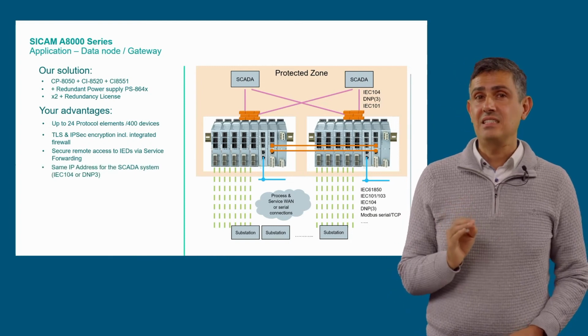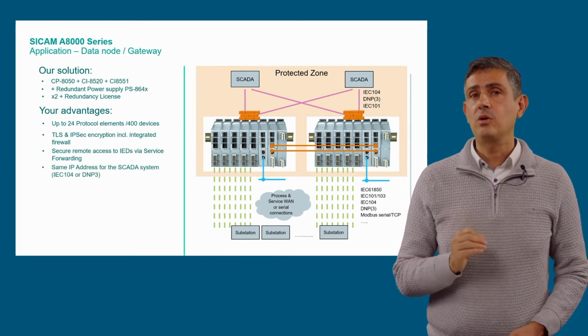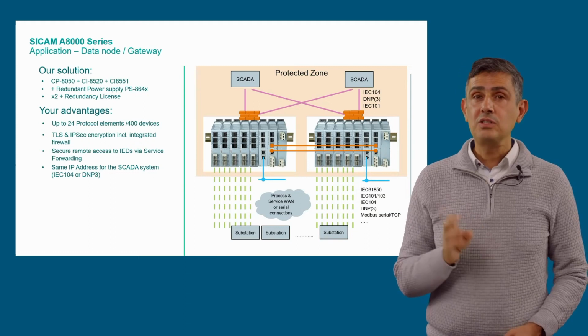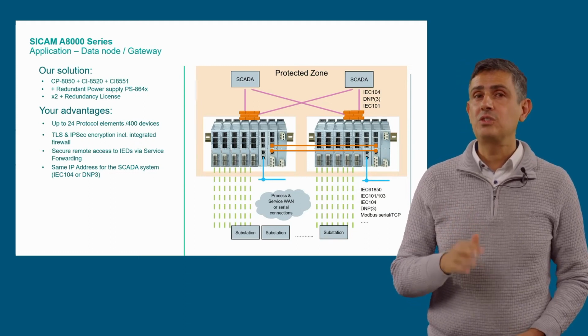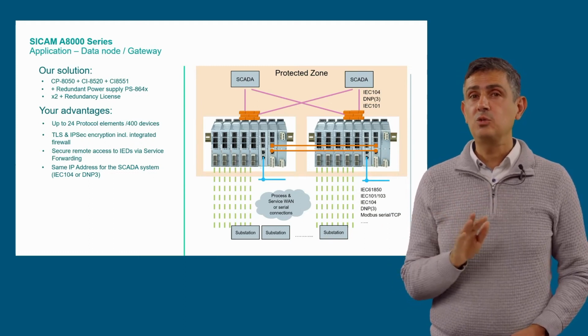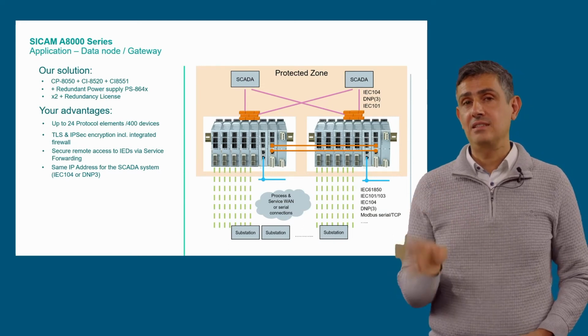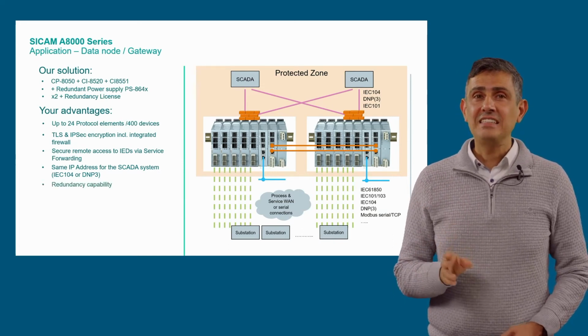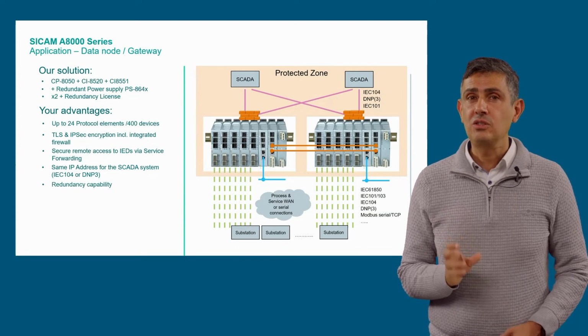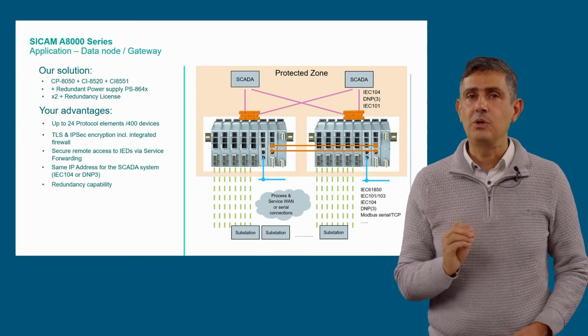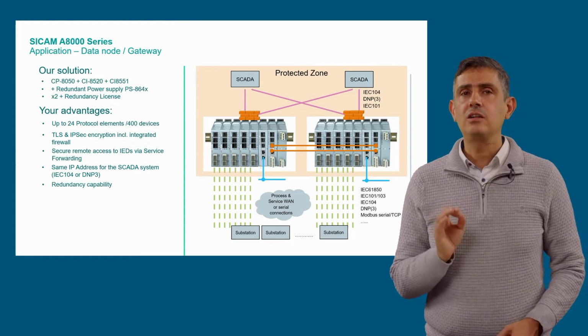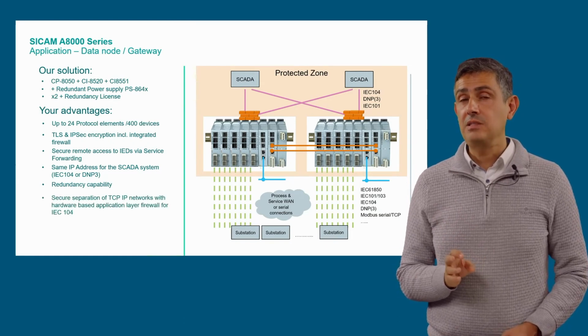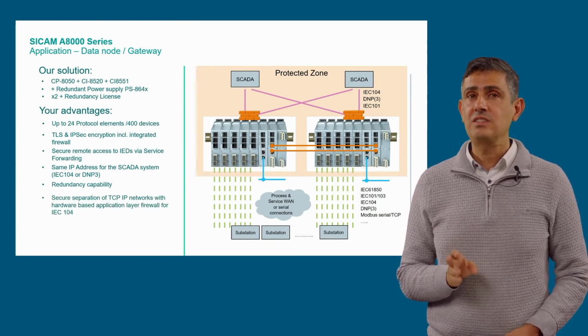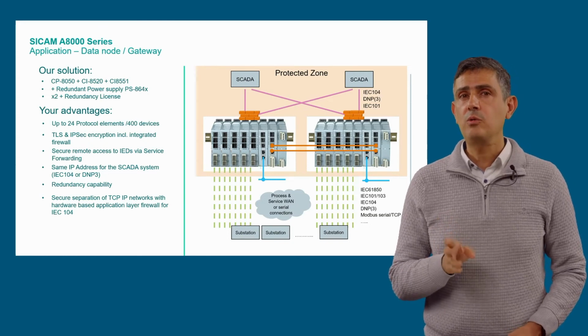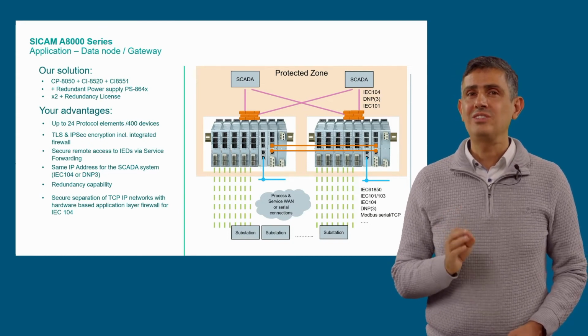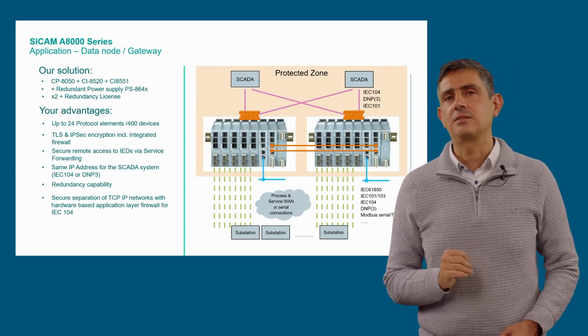If the master system uses the communication protocol IEC104 or DNP3, it is possible to manage the same IP address on both CP8050, so both data nodes will be seen as a single one by the master system. The fact that the redundancy is firmware-based ensures that its implementation is very simple and that it works only under proven algorithms. The CP8050 can also provide a secure separation of TCP/IP networks through the available hardware-based application firewall to ensure the highest cybersecurity to the data center.